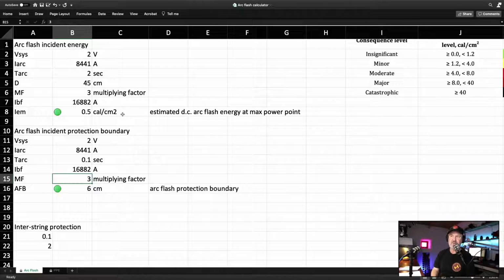Amazing. For those of you who have actually put a spanner across a large 2 volt cell, they will know there will be an arc, but it's more of a melting and burning issue than an arc flash issue. So it's still dangerous. You can still burn yourself, and if you are wearing any metal jewelry, very serious burns can occur if they contact those cells. So it's not to say that it's perfectly safe. It's just that you're below the threshold for PPE. So it would be just basic safe work methods, protecting your hands and eyes from materials that you're working with. So that's at the 2 volt point.